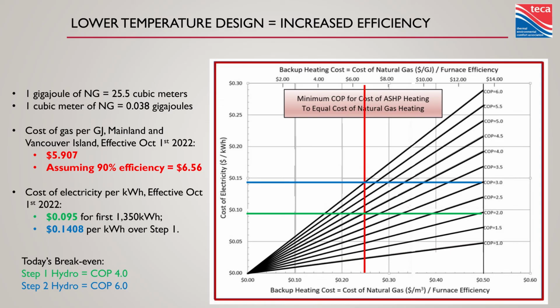Today on step 2, and what we're paying for gas, a COP of 6 is probably going to be that break-even with a 90% combustion efficiency appliance. Step 1, going to be more like a COP of 4. But that is going to change. Our electric rates are going to change, our gas rates are going to change, technology is going to get better. This is just the break-even point against what's said to be the cheapest way to heat right now.